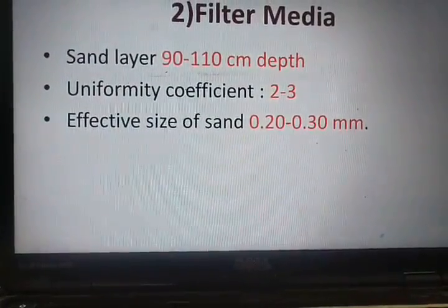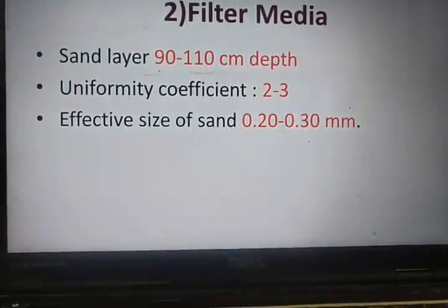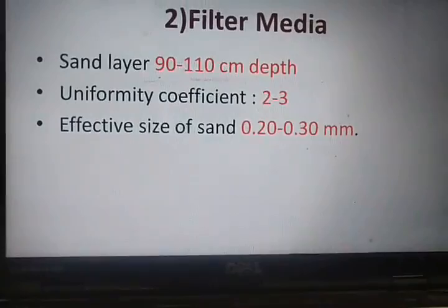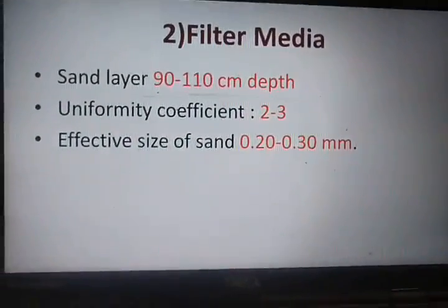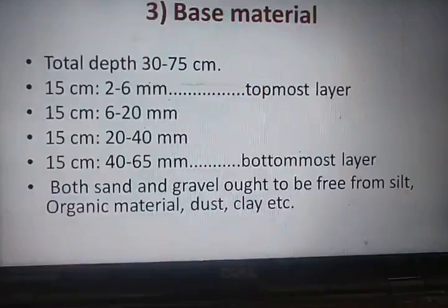Only that sand should be used as a filter media, and the effective size of the sand should be in the order of 0.2 to 0.3 mm. That should be the characteristics of the filter media.